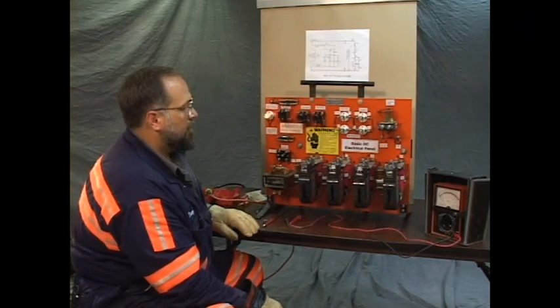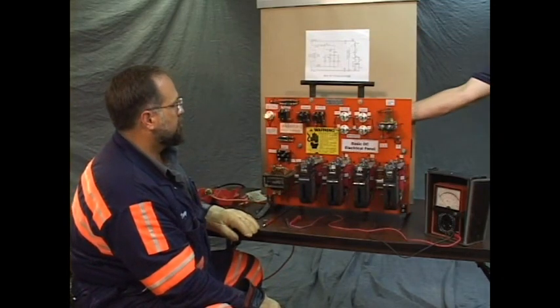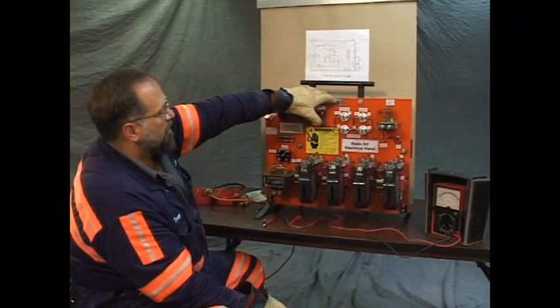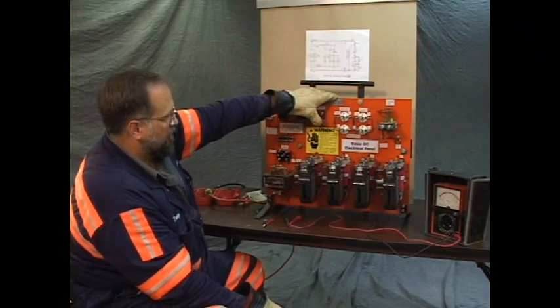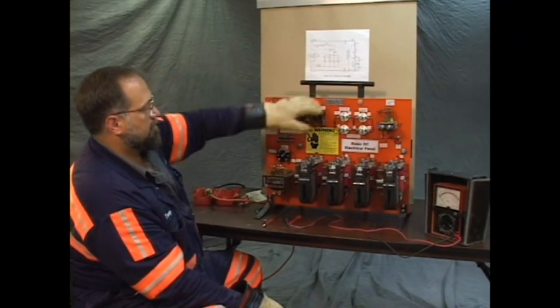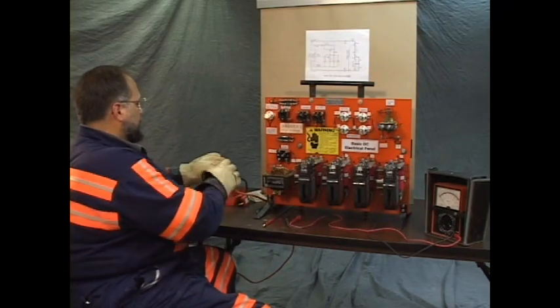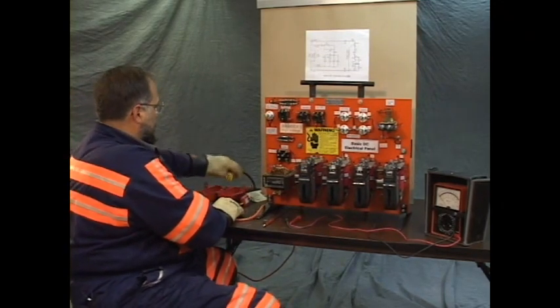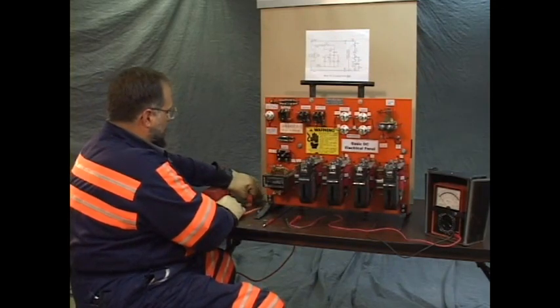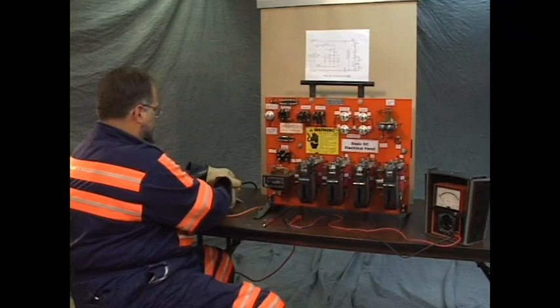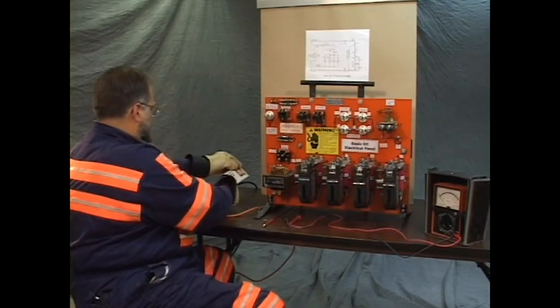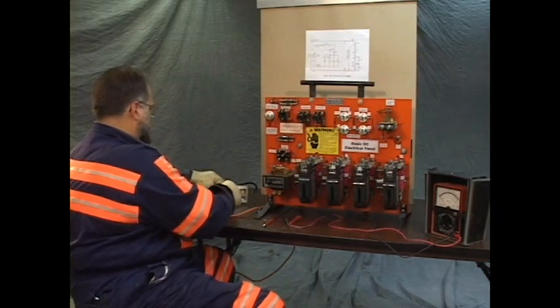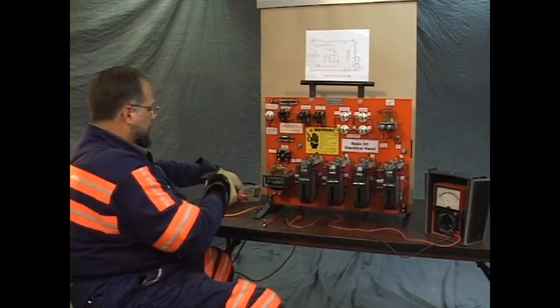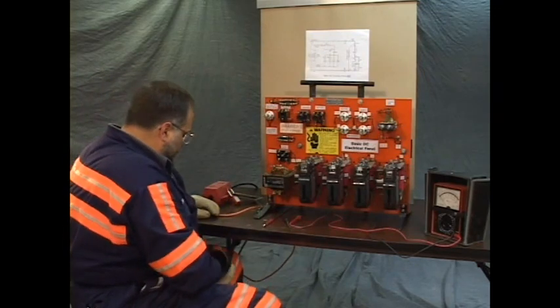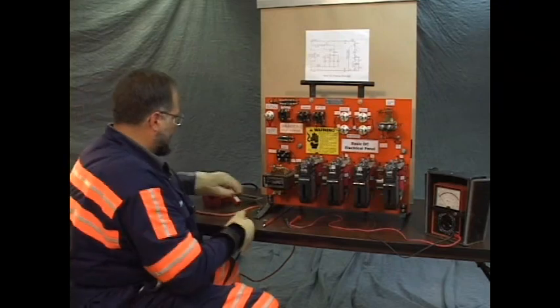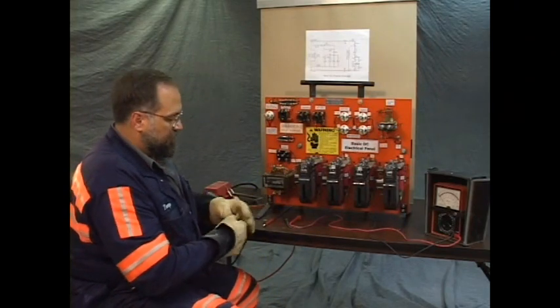Okay. Now with the problem installed, toggle switch number 6 is thrown on the back of the panel. You depress the start switch and nothing happens. Okay, let's remove the power. We're going to lock and tag. Don't forget to take the key from the lock. I'm going to use the tick tracer here to make sure that we have no power.